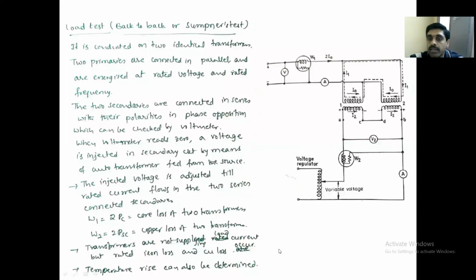Another point is this test is used to find out the temperature rise. How? These transformers will be run back to back for 48 hours. For every 1 hour, the oil temperature will be measured. Based upon the oil temperature, the temperature rise will be calculated. So this is about Sumpner's test.